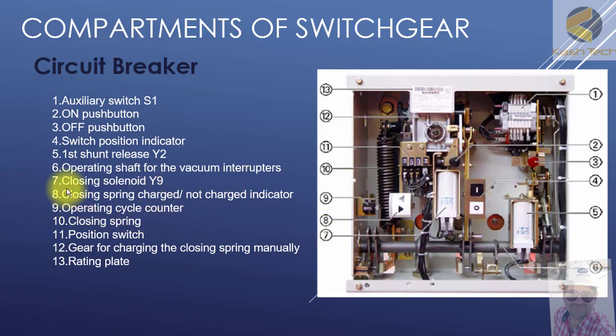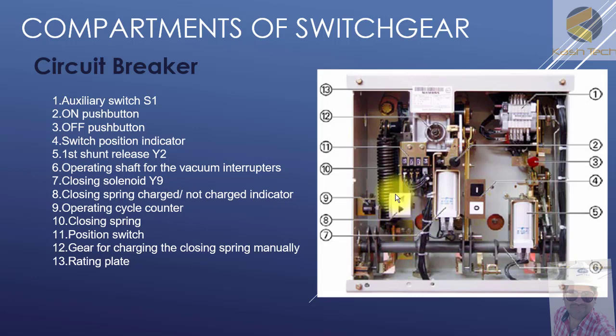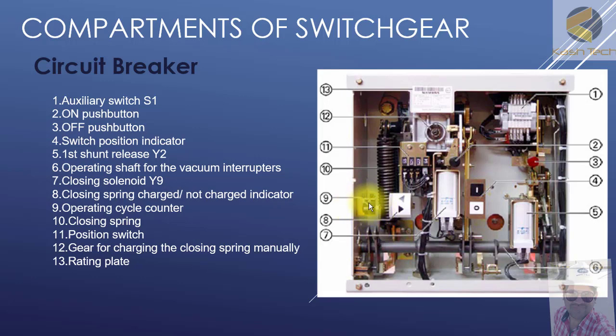Number seven is the closing coil Y9. Number eight is the closing spring charge or not-charged indicator — you can see this indicator marking whether the spring is charged or not. Number nine is the operating cycle counter, which shows how many times the breaker has been operated.